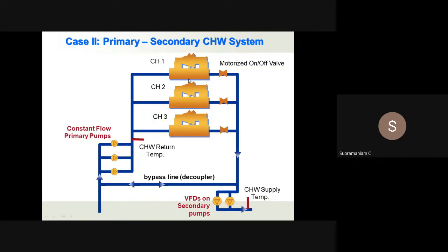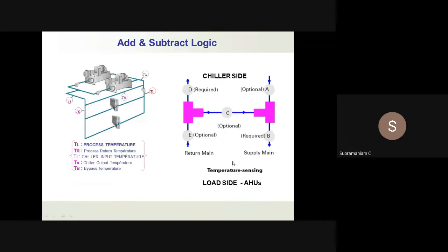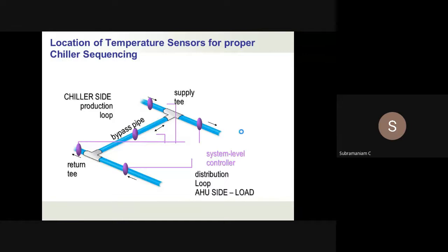The top side is, you are producing chilled water with primary pumps attached to the chiller. The secondary pumps, the distribution pumps, are with VFDs, which go to the system there. And there is a bypass line where there is no valve. Chilled water can flow either left to right or right to left based on the difference between primary flow and secondary flow. So here the chillers are controlled based on the leaving chilled water supply temperature, and the subtraction of chillers is controlled based on the delta T of that. That's what we will see here.